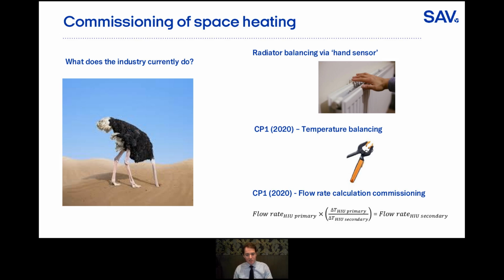CP1 does recognize this and say, actually, there are some flaws to temperature balancing, so the way that we can do it is via flow rate. But without that visibility into actually seeing flow rate, the best we can do is trying to do it via calculation. So looking at the primary side of the heat exchanger, you can look at your flow rate and your delta T, and using this equation along with those temperature clamps, you can now do a flow rate calculation for that secondary side.